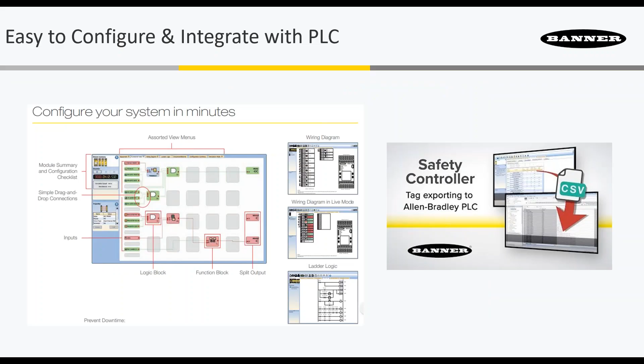Yeah, that's a good point. It's like if you're familiar with light curtains when they're cascaded - the OSSD outputs from this device feed into the inputs of the next one, and its outputs are based on what happens on the one before it, sending its OSSDs on or off to the next, and so on. So from a safety standpoint, the OSSDs work just like a cascaded light curtain, and the diagnostic data rides on those OSSD wires. Every device has its own safety output - that's important to remember.